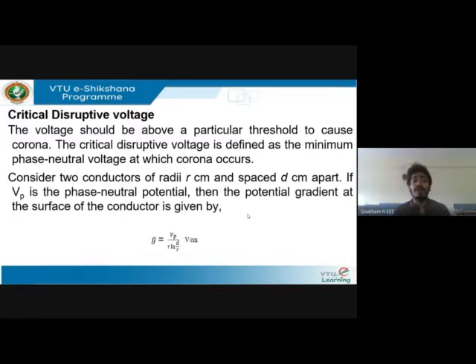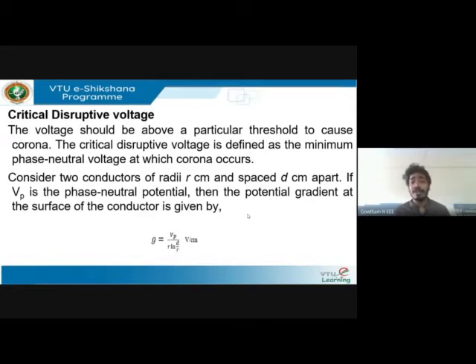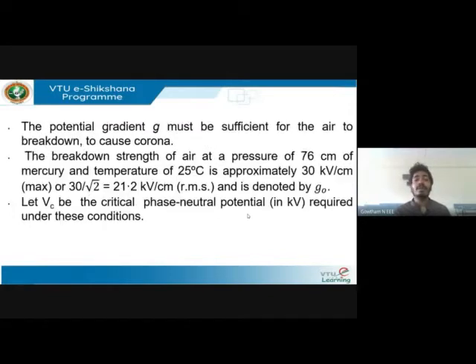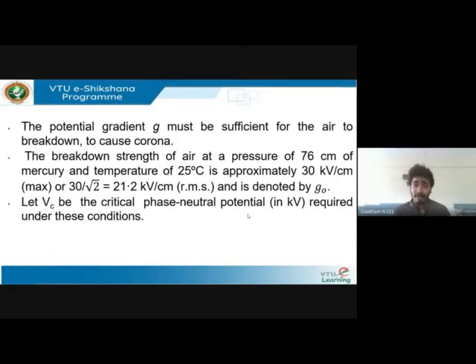To derive the expression, consider two conductors of radii r centimeters spaced at a distance d centimeters apart. Let Vp be the phase-to-neutral potential. The potential gradient g at the surface of the conductor is: g = Vp / (r · ln(d/r)) volts per centimeter. This potential gradient g must be sufficient for the air to break down. The breakdown strength of air at a pressure of 76 cm of mercury and 25°C is approximately 30 kV per centimeter.